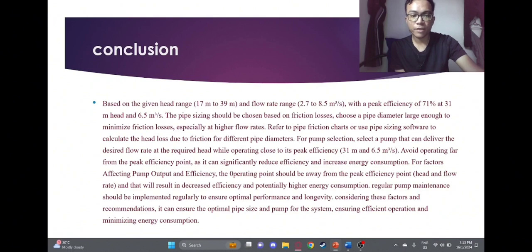Avoid operating far from the peak efficiency point as it can significantly reduce efficiency and increase energy consumption. For factors affecting pump output and efficiency, an operating point away from the peak efficiency point will result in decreased efficiency and potentially higher energy consumption. Regular pump maintenance should be implemented to ensure optimal performance and longevity. Considering these factors and recommendations, we can ensure the optimal pipe size and pump for the system, ensuring efficient operation and minimizing energy consumption. That's all from us.